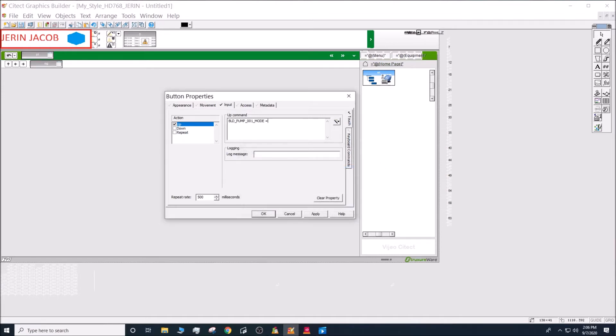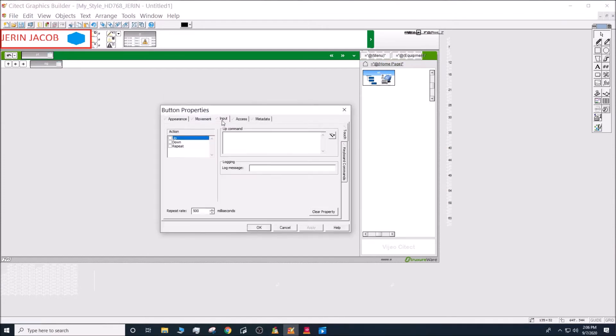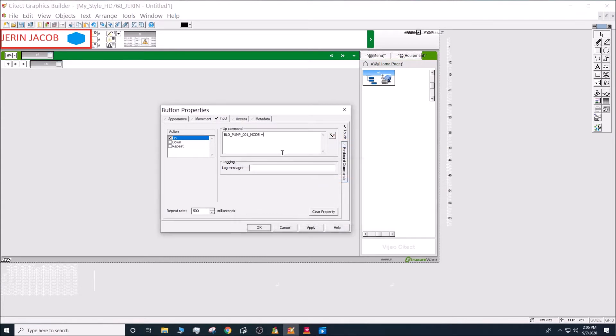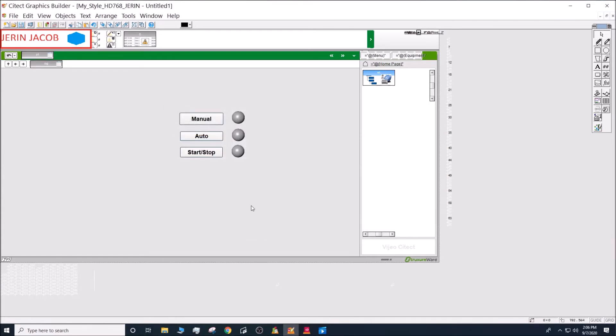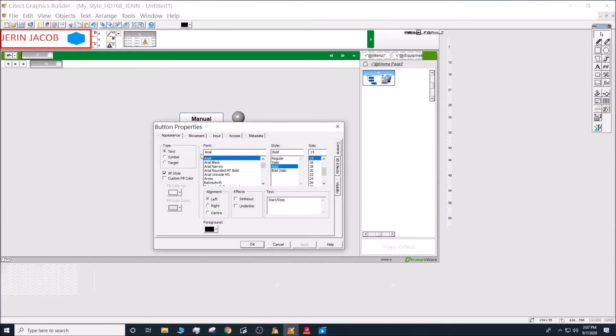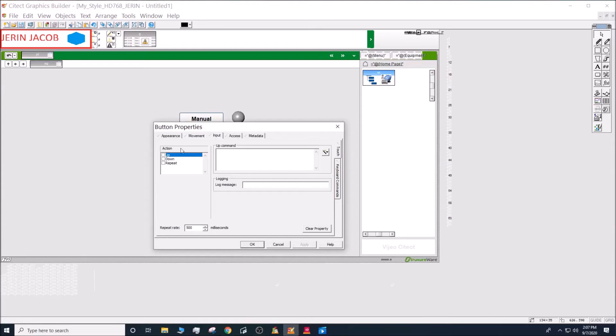Go back to your button, click the magic wand, select 'Insert Tag', and you'll be able to see your tags. Pick 'building_pump_mode' and for Manual set the value to zero. For the Auto button, go to the Input tab, select the Up action, open the magic wand, and select the mode tag, setting it to one.